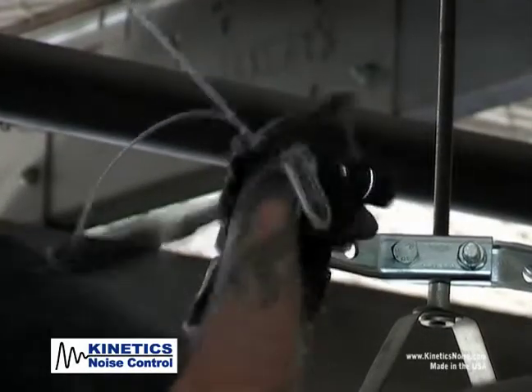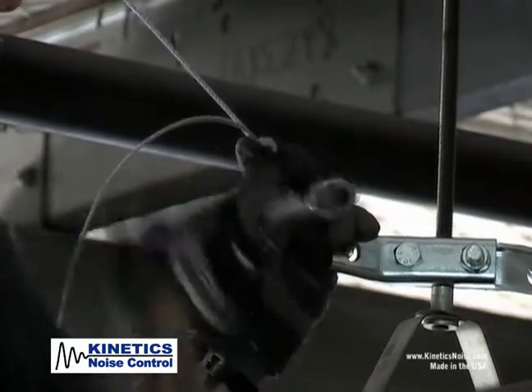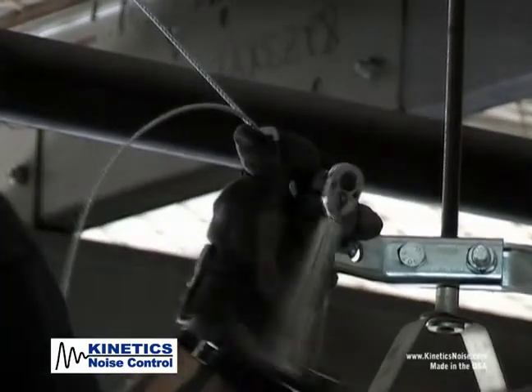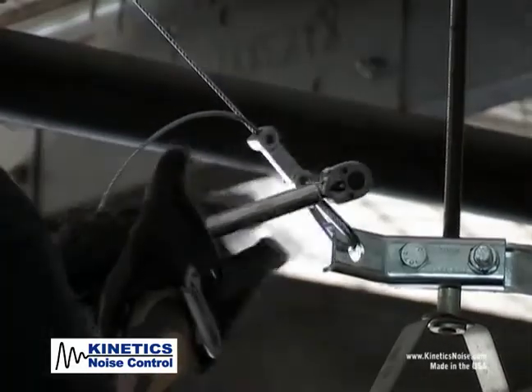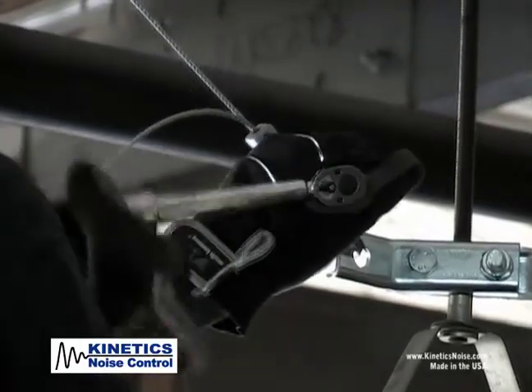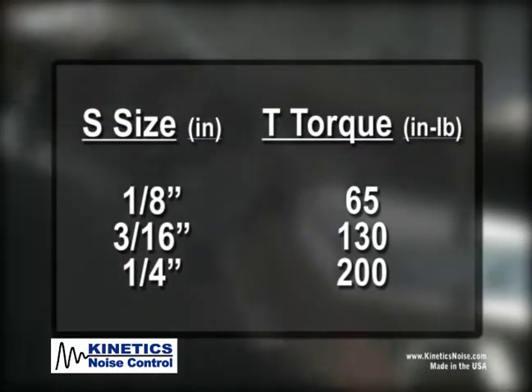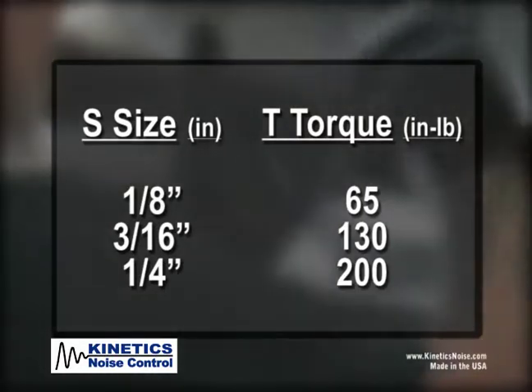Finger tighten all set screws to hold the cable in place. Fully seat the set screws by using a tool to torque the set screws to the appropriate torque for the size of the cable. Start with the set screw closest to the loop and work out to the tail end of the cable.